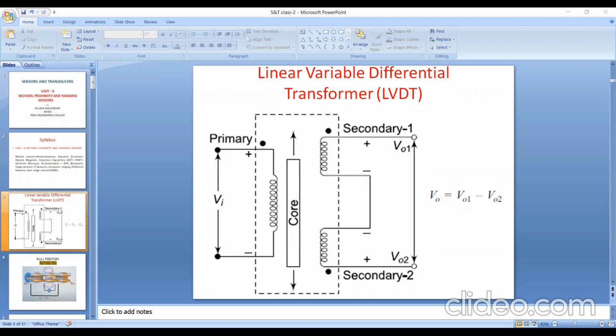Now moving to the construction of the linear variable differential transducer, it consists of a single primary winding, and two secondary windings, S1 and S2. It is wound on a cylindrical former. When a sinusoidal voltage is applied to the primary winding, we are exciting the primary winding. The two secondary windings have an equal number of turns, they are identical, and they are placed on either side of the primary winding. The primary winding is connected to an alternating voltage source.